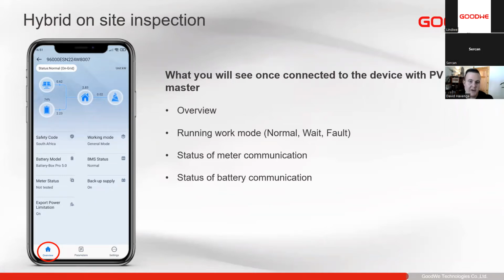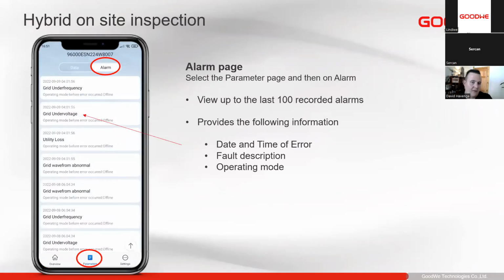So next with PV Master, we can see the alarms. If we are experiencing a problem on site, it's always best to go and view the alarms that we are experiencing. So you'll see in the bottom, we just go to parameters. Parameters will open in the data tab, and then we go to the alarms tab. Under the alarms tab, it will show you up to the last 100 recorded alarms.